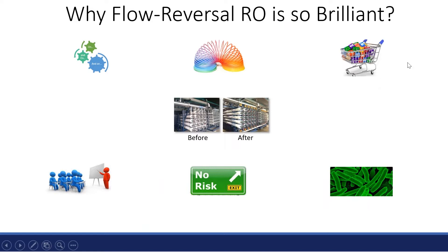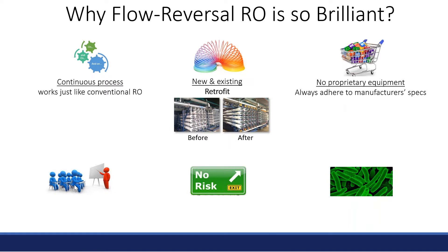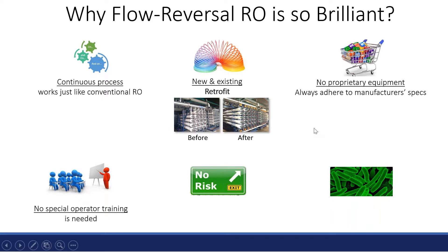Flow reversal is a continuous process that works just like conventional RO. It can be implemented for new RO systems or existing systems by retrofit — a big differentiator for this technology. We do not need proprietary equipment because we always adhere to manufacturer specs. There is no need for special operator training, and there is low risk because we have 100% fallback: at any point, if we don't want high recovery for some reason, we can go back and operate the exact same flow reversal machine as a conventional RO system. Experience in the field also shows the process reduces biofouling and chemical use.